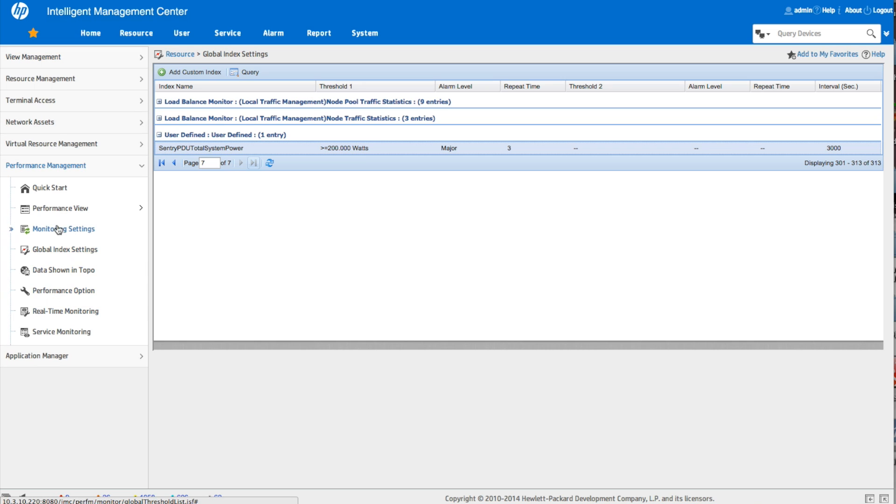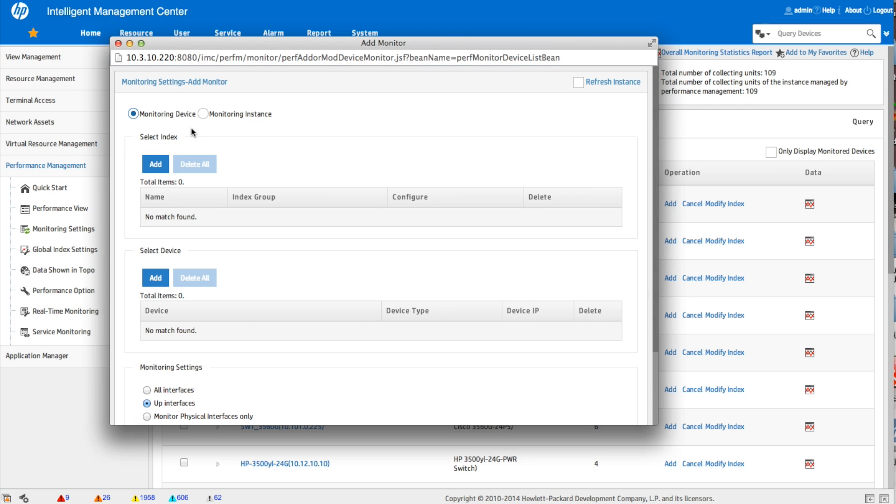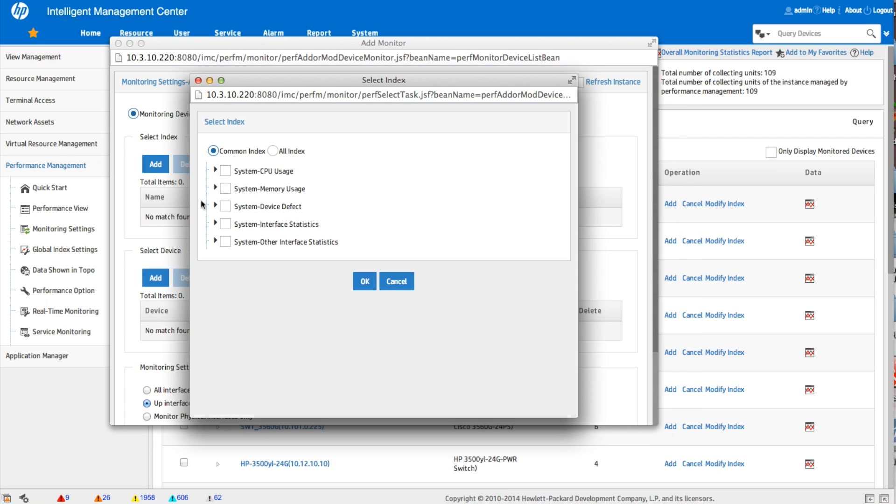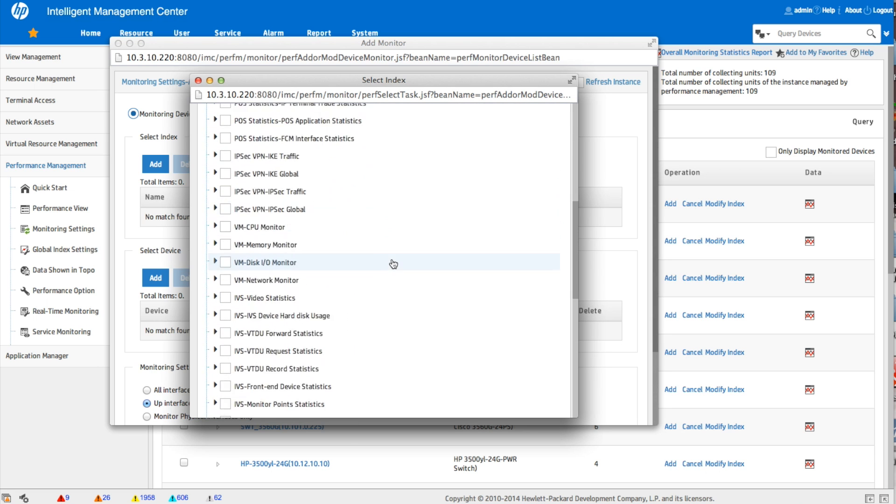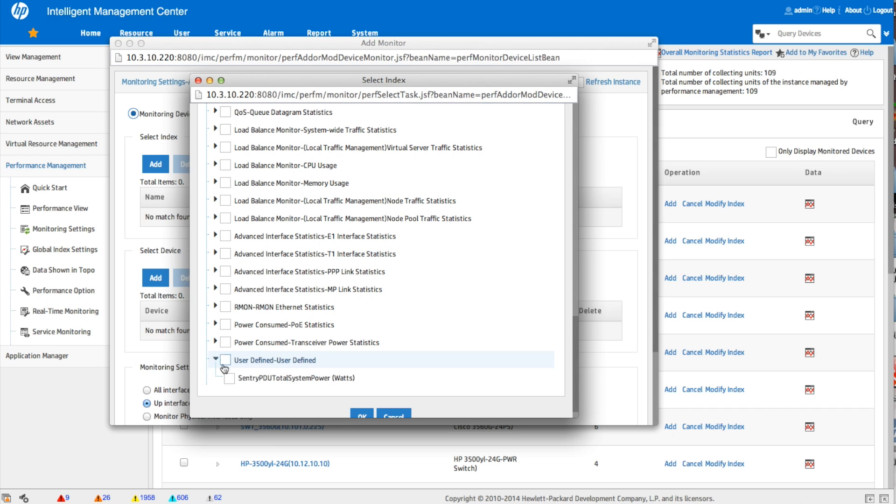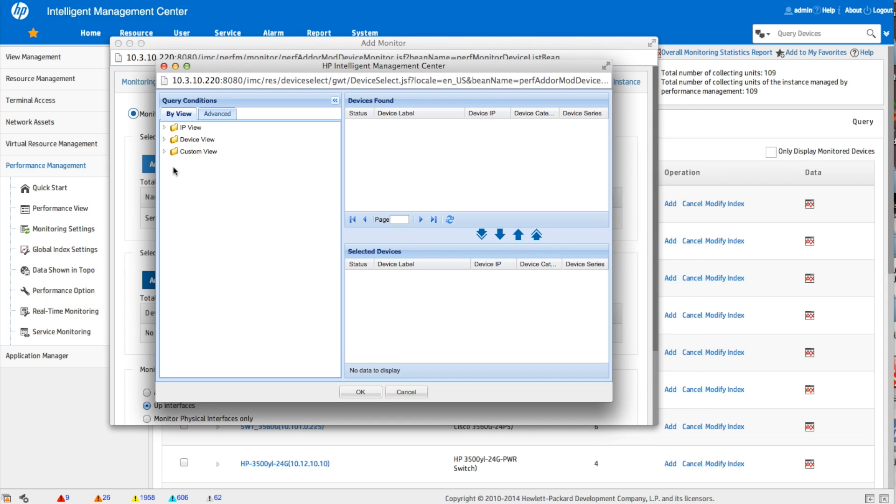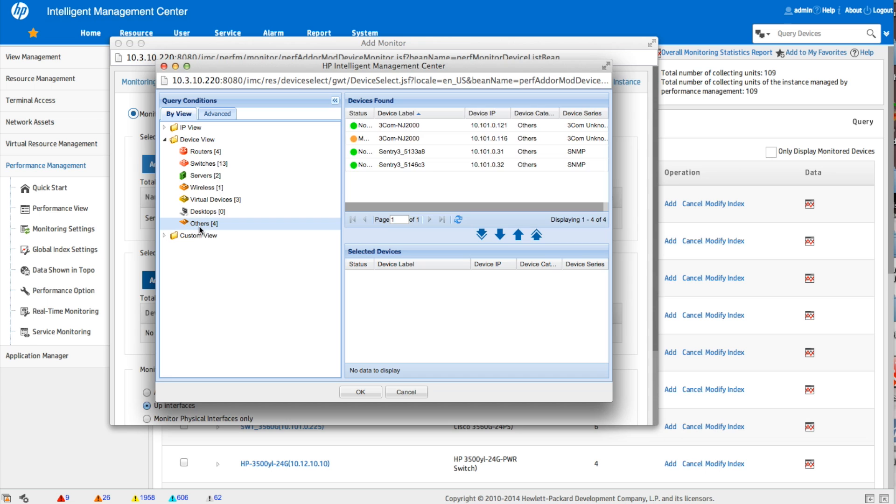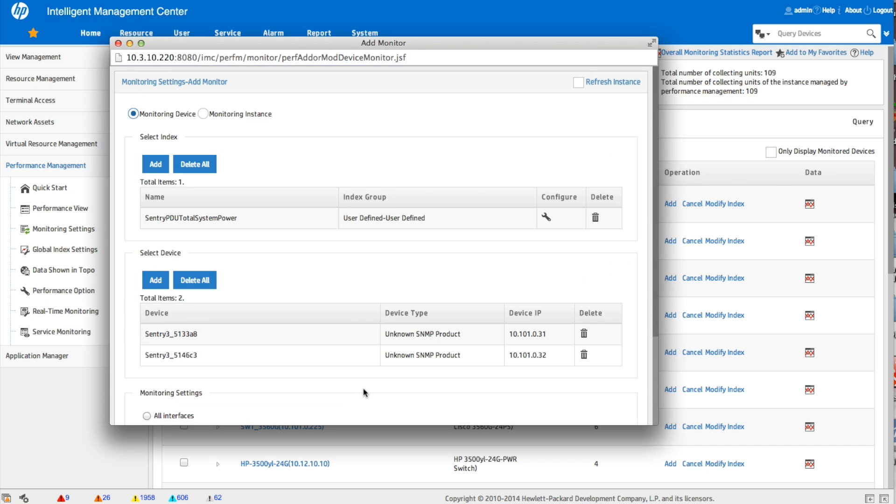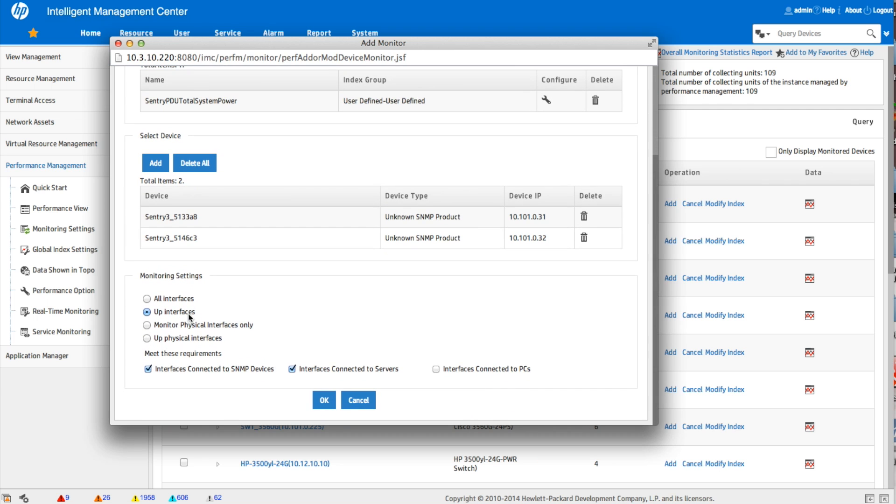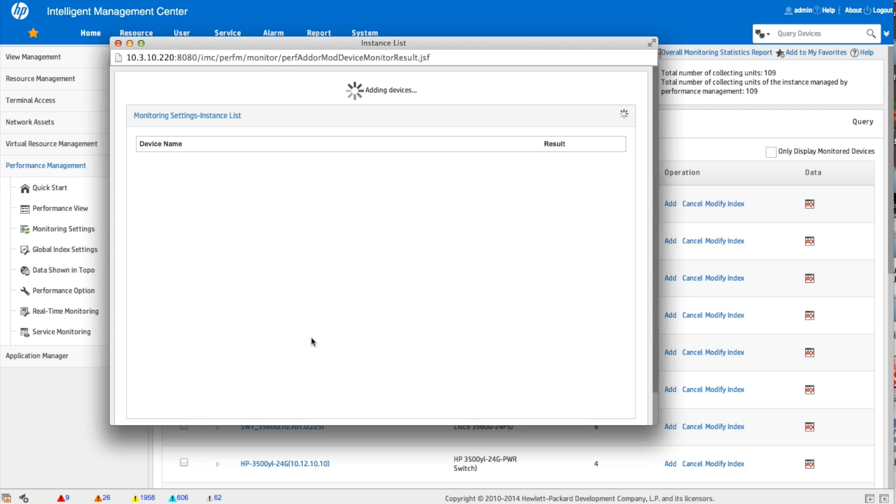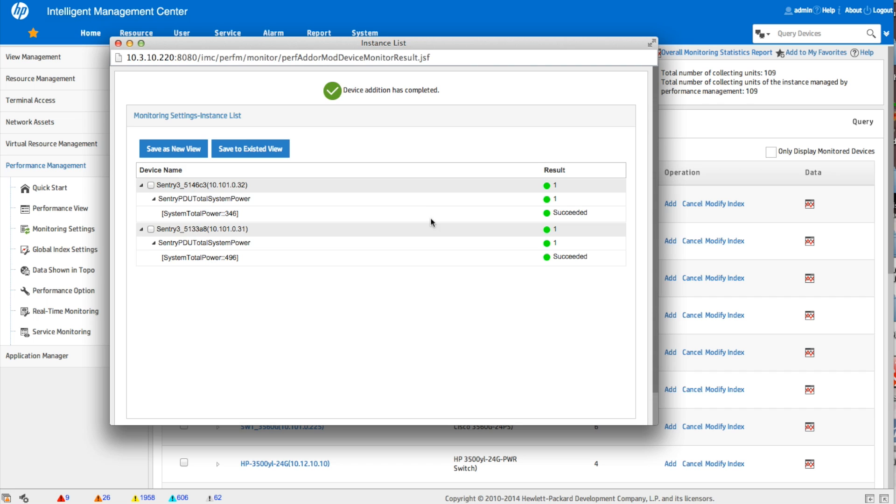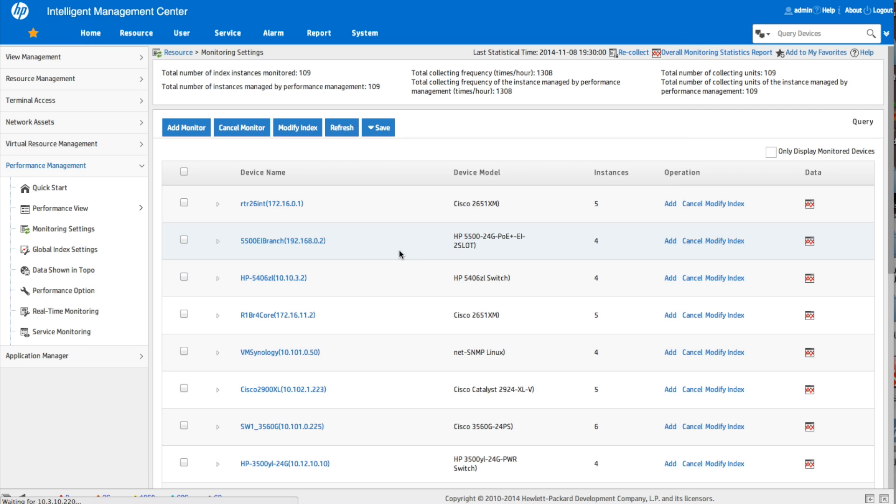So now that we've set up the thresholds, the next step here is to actually start tracking this on a couple of devices. So you saw earlier, we had two of those PDUs, so we're going to go add monitor. We're going to select the specific index we want. So by default, it won't show up. We're only showing the common indexes. You have to click on the all index button, go to the bottom, and then select that Sentry PDU total system power. So there's that descriptive name that we wanted to make sure that was really clear. Naming is very important. Select the device. Select the second device. Click OK. Now all of these monitoring settings here, these really matter a lot more when you're doing things on interfaces. In this case, it really doesn't apply, but we're just going to click OK. Succeeded, succeeded. Now we click close.